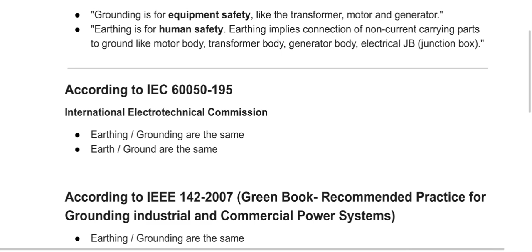So we discussed four standards: IEC 60050-195, IEEE 142-2007, IS 3043-2018, and CBIP 334. All four say earthing and grounding are the same. Whether we say neutral earth or neutral ground, or motor body earth or motor body ground, they have the same meaning.